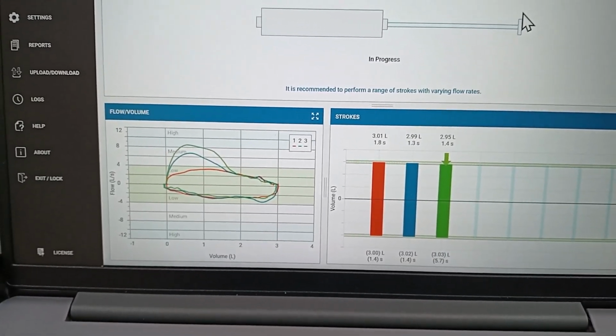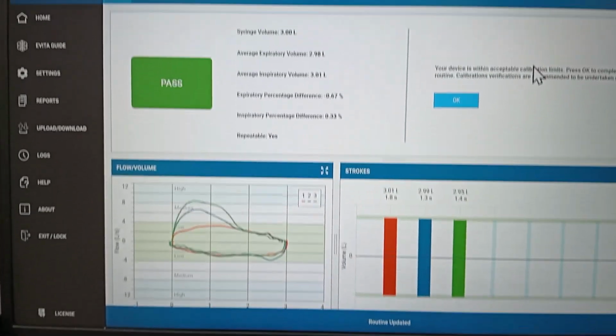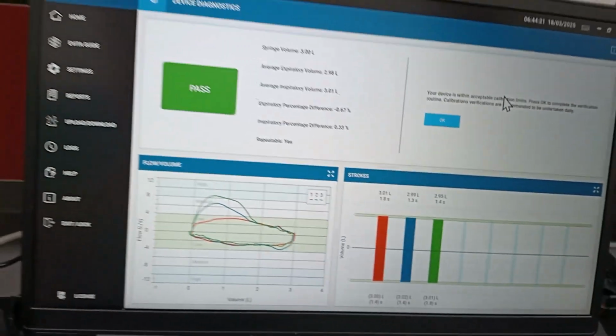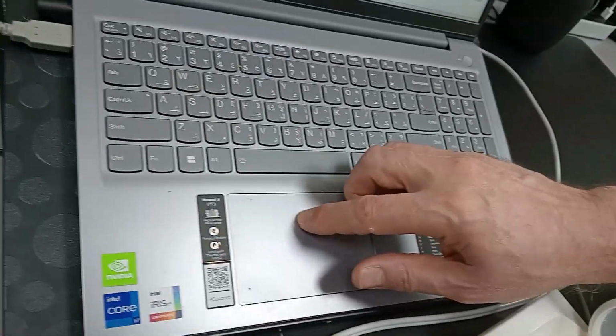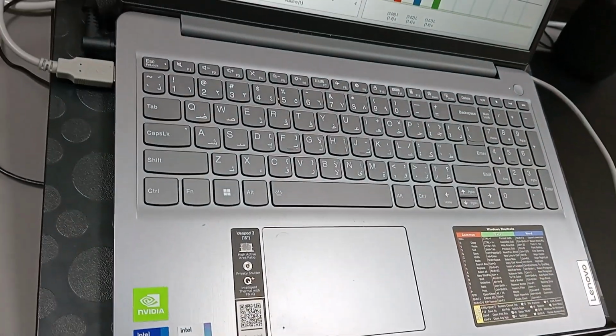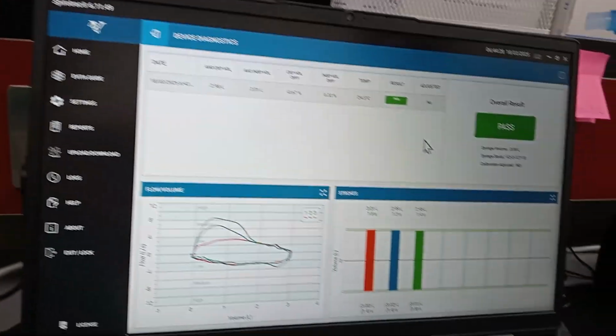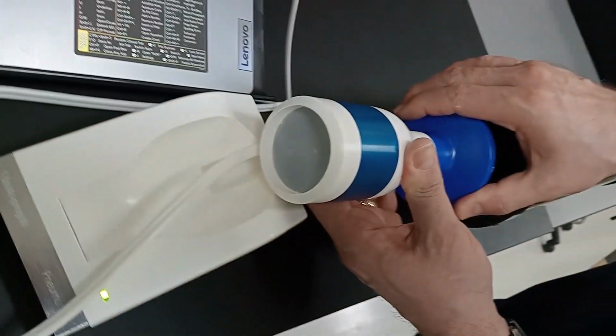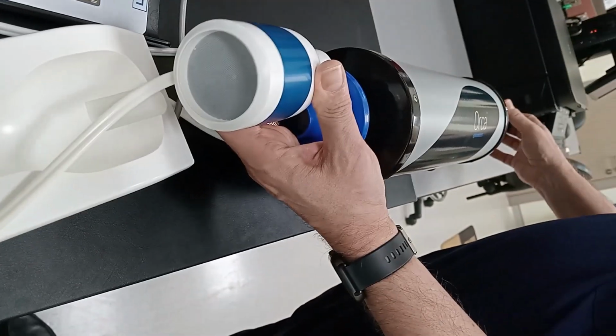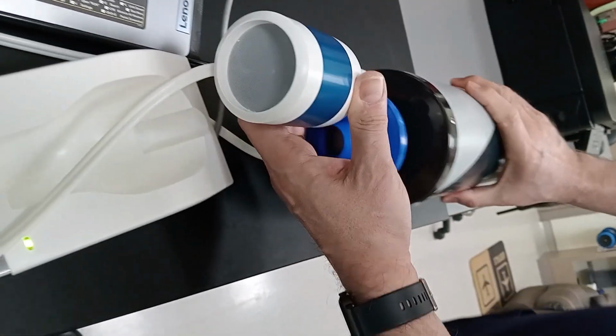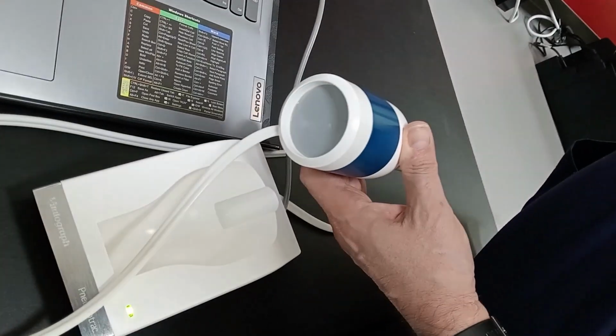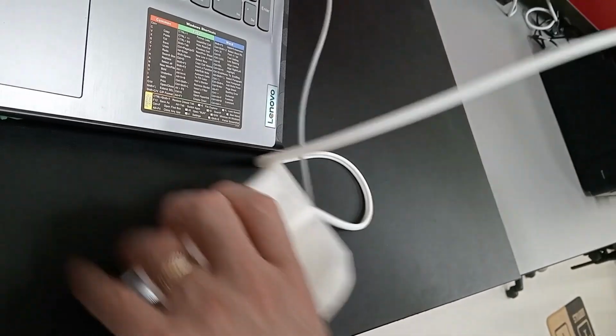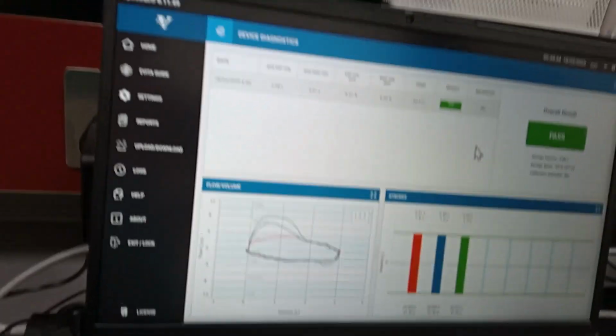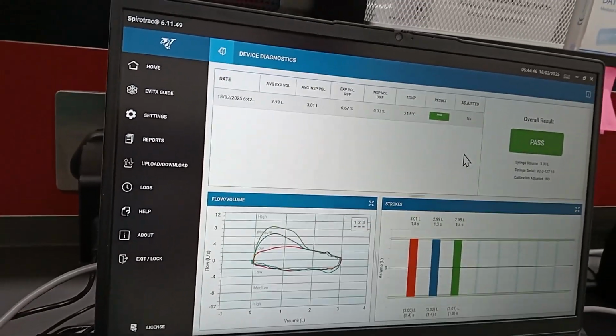At this point, it often will approve the calibration, as it has done here, or it may ask for additional calibrations. So here we indicate that the device has passed the test, and we can disconnect the Vitalograph from the 3-liter syringe, which we then place away. So the device is now ready for the patient, and the patient's information now needs to be set up.